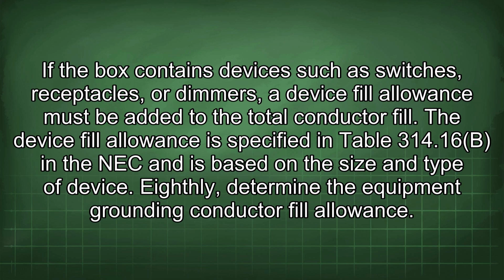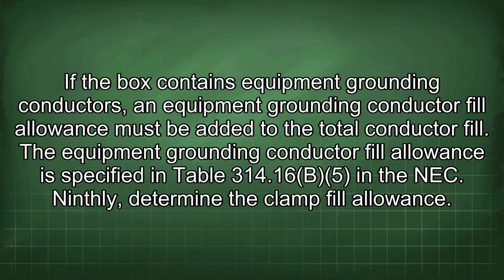Eighthly, determine the equipment grounding conductor fill allowance. If the box contains equipment grounding conductors, an equipment grounding conductor fill allowance must be added to the total conductor fill. The equipment grounding conductor fill allowance is specified in Table 314.16(B)(5) in the NEC.